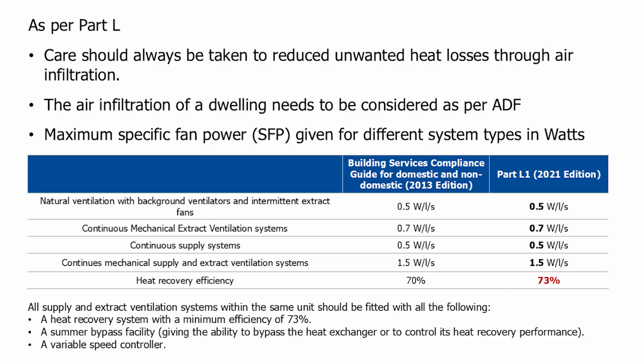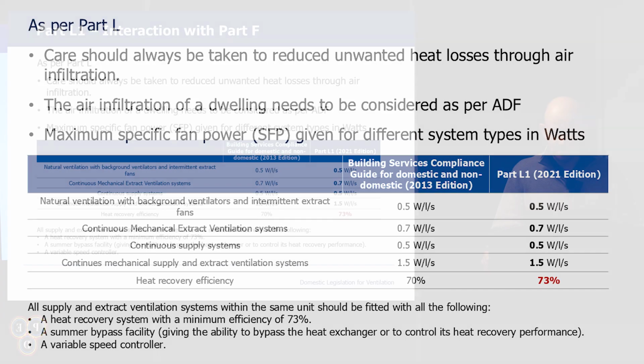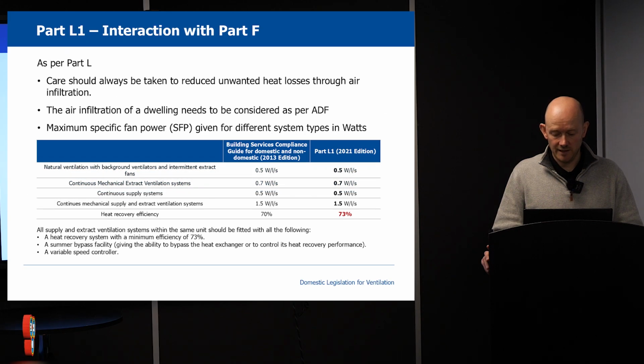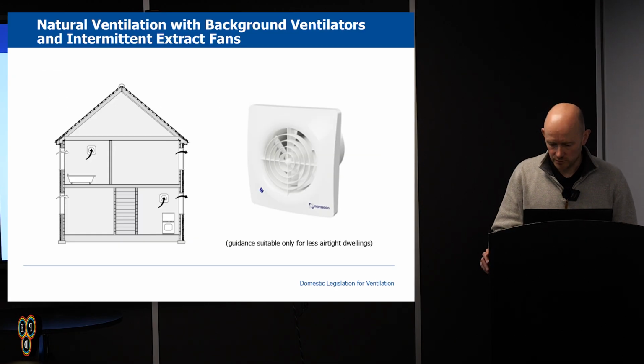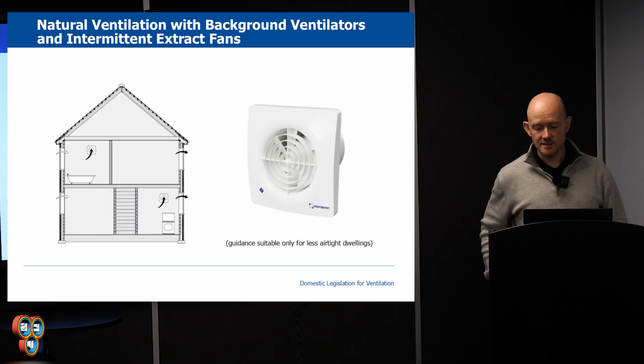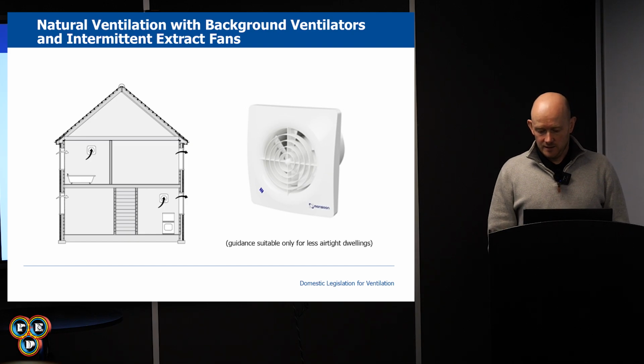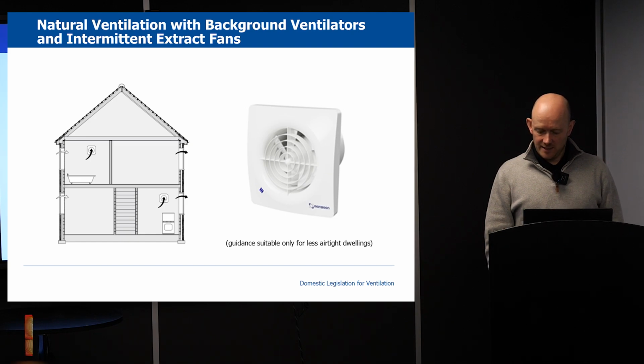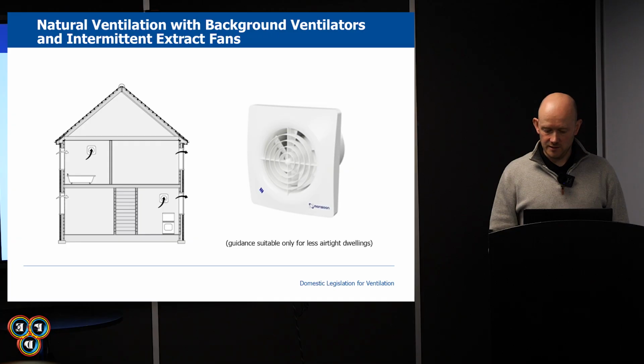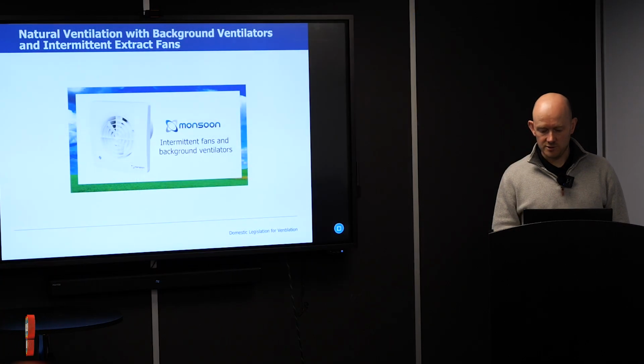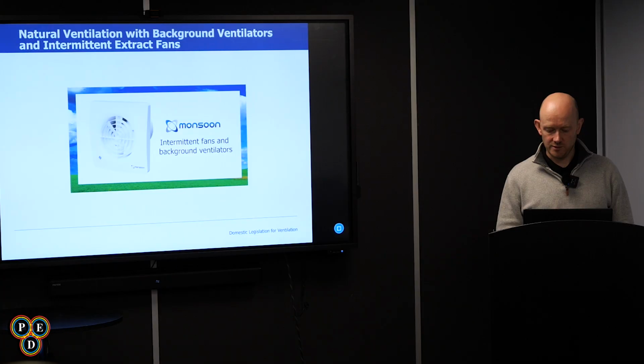There continues to be a requirement to have summer bypass and variable speed controller for supply and extract ventilation systems within SAP. Natural ventilation with background ventilators and intermittent extract fans, known as System 1. Intermittent extract fans should be fitted in all wet rooms, and correctly sized background ventilators, also known as trickle vents, should be installed and sized correctly. Here is an animation of a natural ventilation, as you can see as part of this animation.